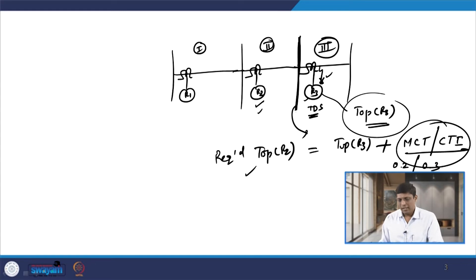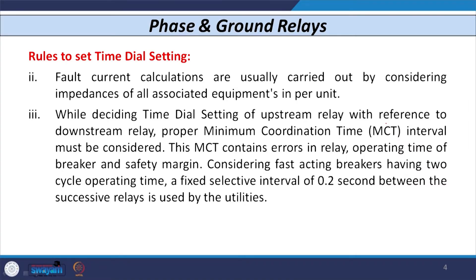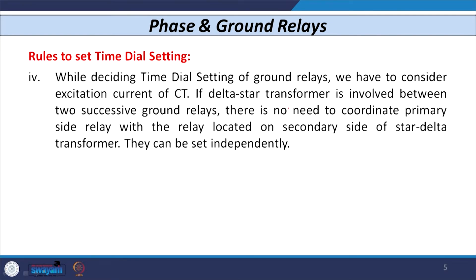We then decide the time of operation of relay R2, and similarly we decide the time of operation of relay R1. The next rule is that while deciding the time dial setting of a ground relay, we need to consider the excitation current of the CT. However, when we consider two successive ground relays and there is a star-delta transformer involved between them, there is no need to consider any such rule.